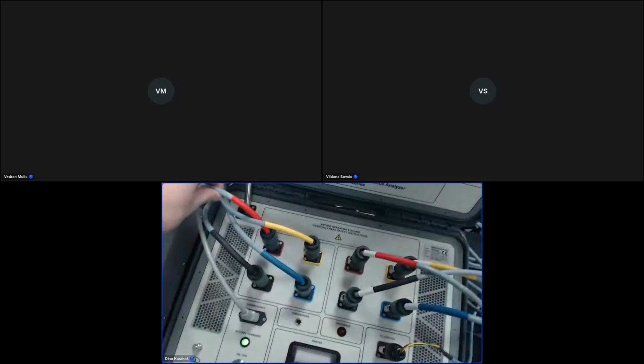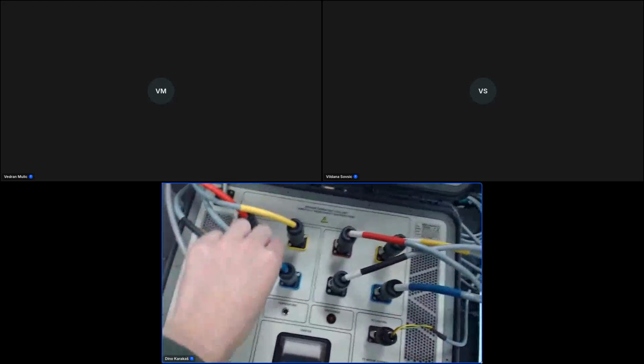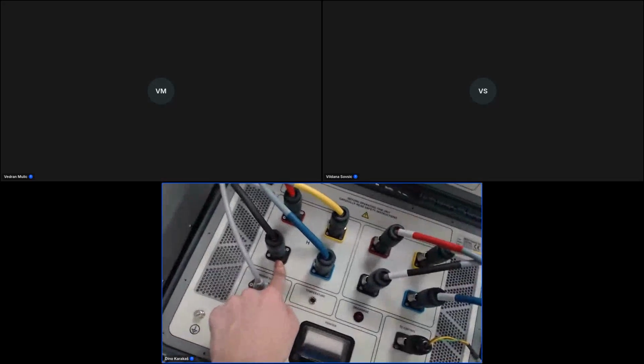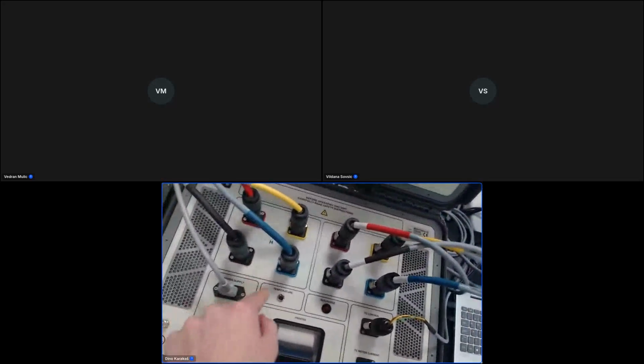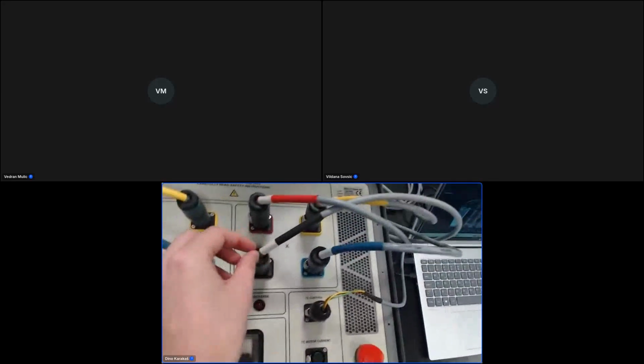So the device is now turned on. You can see the cables again. You see the coloring matches here: red, yellow, blue, and black. Black one goes to the neutral point. The same is for low voltage side. For low voltage side, cables are different because they have this white coloring, and it's connected to this transformer. This transformer, you can see this is a tap changer simulator. So we will show functionalities of device with testing transformer with tap changer.